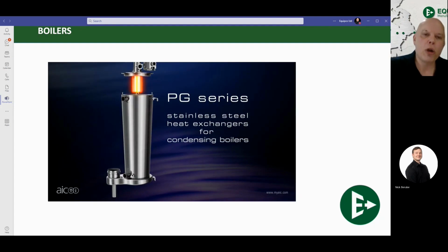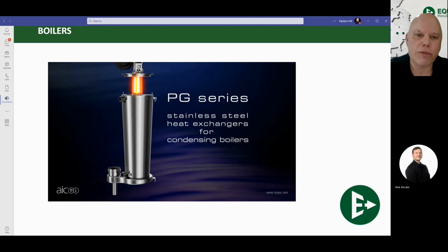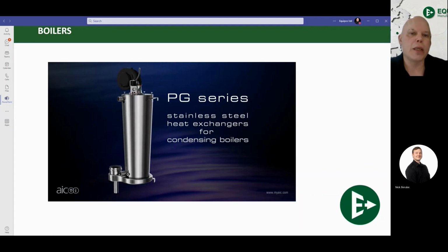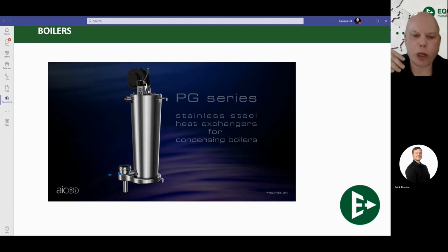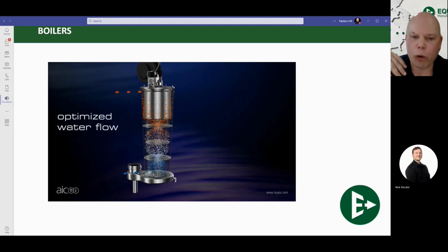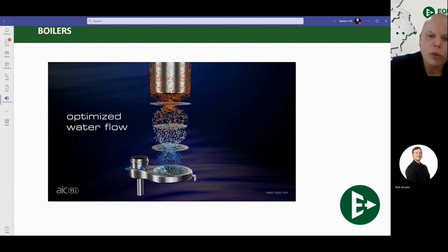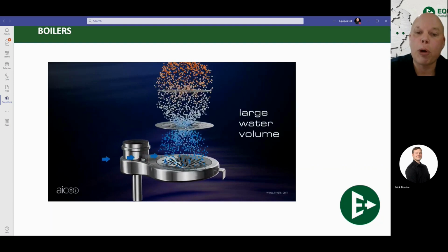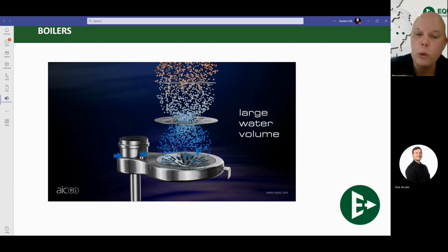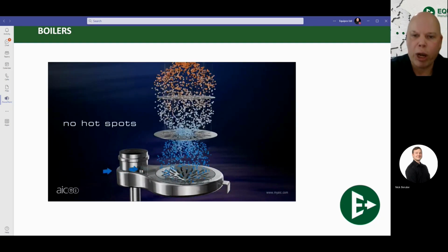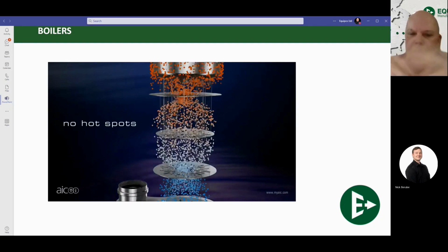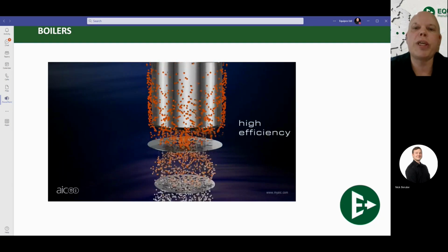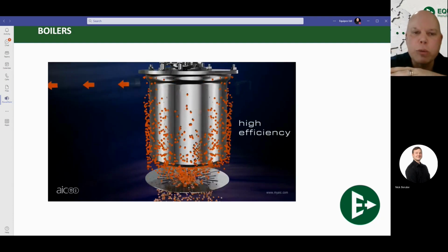Here comes our burner. We are a down-fired burner on these fire tube heat exchangers, and we're going to walk you right through what's happening in here. So here comes the cold water returning. We're beneath that 135, so we are going to be condensing. We are starting to heat from the bottom up, using the coolest water to pre-warm that water. As we move up inside that heat exchanger, the flue gases are hotter and hotter until we get our output temperature as desired.